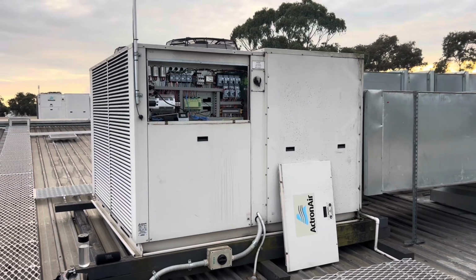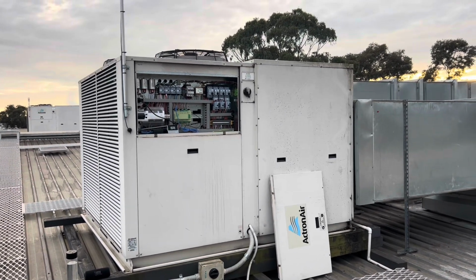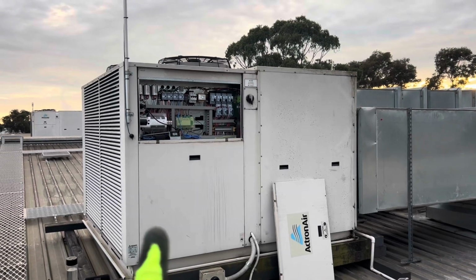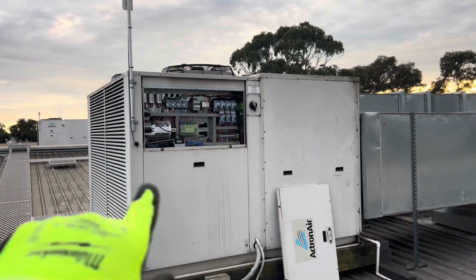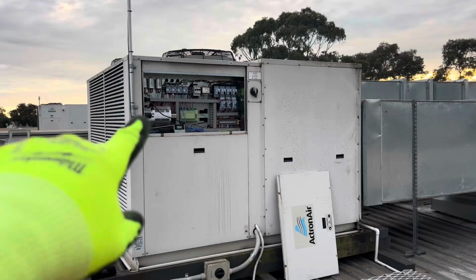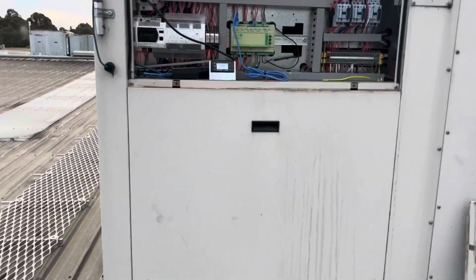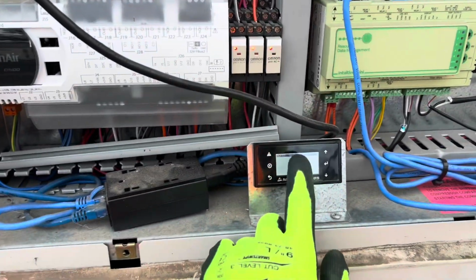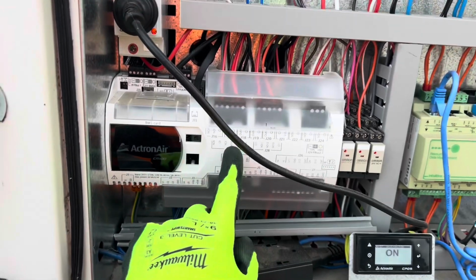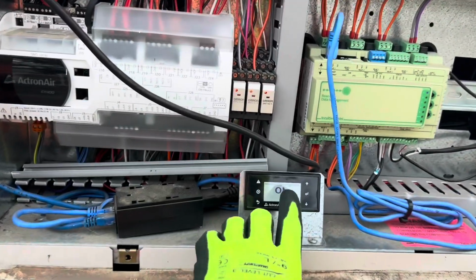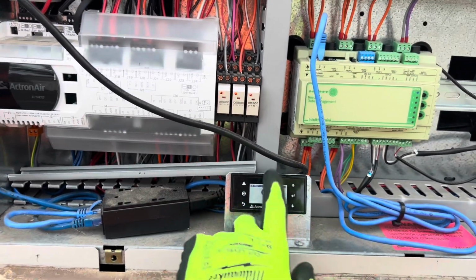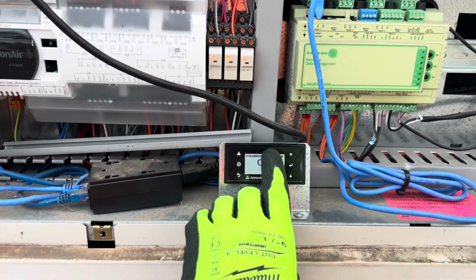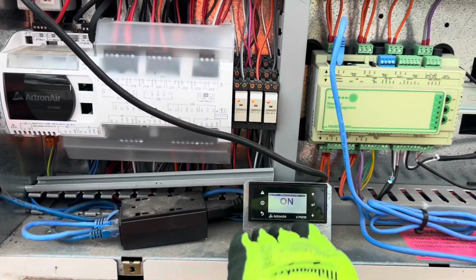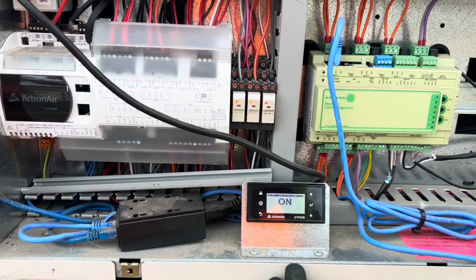So I looked at the airflow, and found that the airflow on this one - for anyone who doesn't know, these CP05 interface with their controller, I'll take you over and have a look - but this CP05 interface here basically gives you access to the parameters in here. Usually you can go in and change, if it's just being run from here, the medium speed to what you want it to be, and that's how it picks a fan speed.